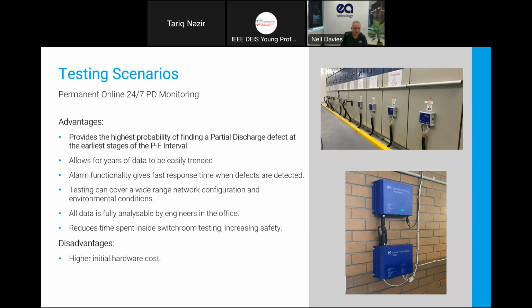The good thing about it from my point of view is that if I've got a monitor on a switchboard I need to assess, I can do that from the office here at any time of the day, rather than having to travel to site and everything. It also reduces the time spent inside the switch room. Typically, a switch room is going to be safe because the probability of failure is still very low, but it's still safer to be in an office environment than standing in front of the switchgear. But of course, there's higher hardware cost involved, so full permanent condition monitoring is not always practical.